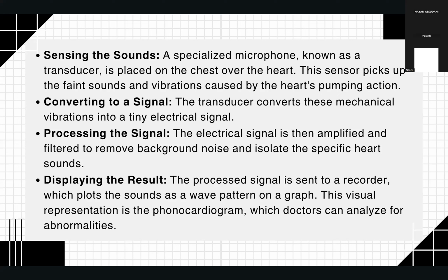With the piezoelectric effect, the sound vibrations squeeze the particles in special crystals and create electrical charges, which are then converted to voltage signals. It works best for the ranges we care about, like 30 to 100 hertz and 100 to 300 hertz, that is for S1 and S2 respectively.